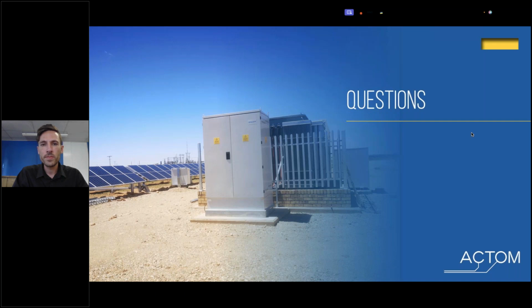Another question from Vernon: how do you integrate the sensors into the transformer, and can manufacturers be influenced to integrate them? This is an advanced transformer, but all the equipment can be installed by the manufacturer on a request basis. Gas analyzers are the most important and most widely used. In this transformer we had a 9-gas analyzer giving us a lot more information, but you could use a smaller one, like a 2-gas analyzer, and do basically the same thing on a smaller scale.